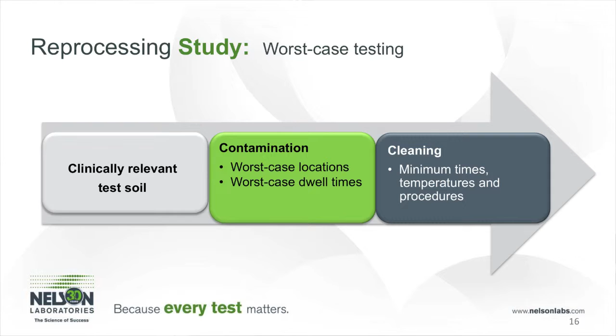FDA's biggest keywords right now are worst case testing and clinical relevance. So we want to make sure that we are doing the worst case testing in all of the parts of the validation. This includes determining a clinically relevant test soil, contamination, and all of the cleaning that we're performing to make sure that the cleaning is the minimum times, temperatures, etc.